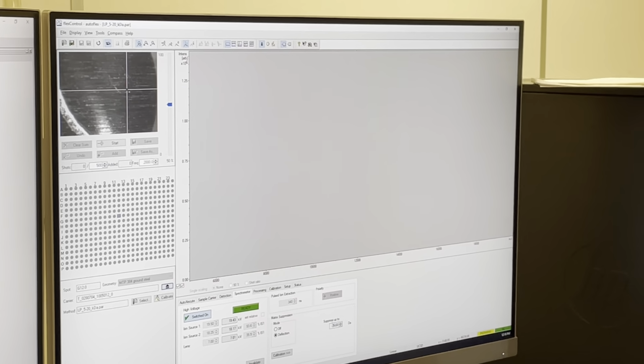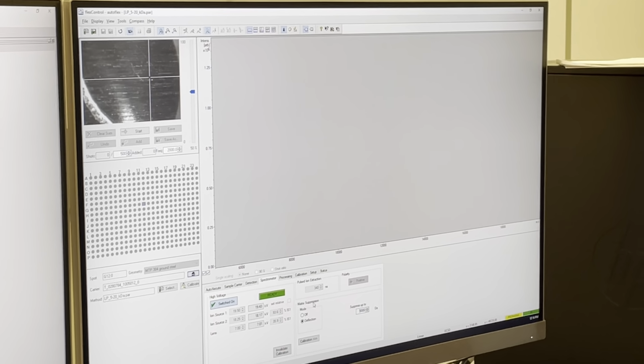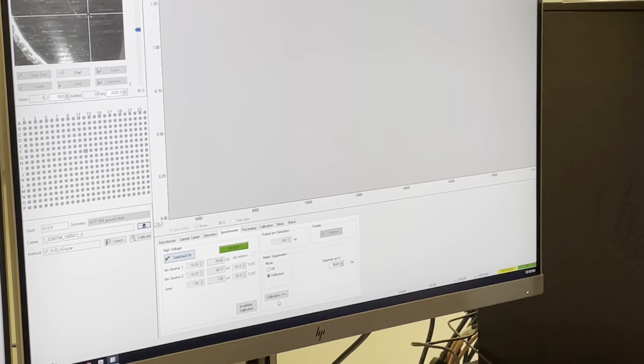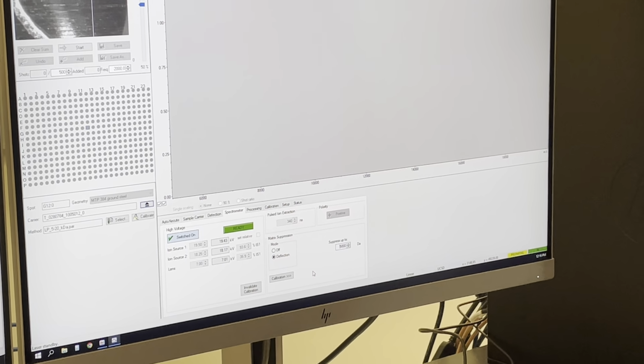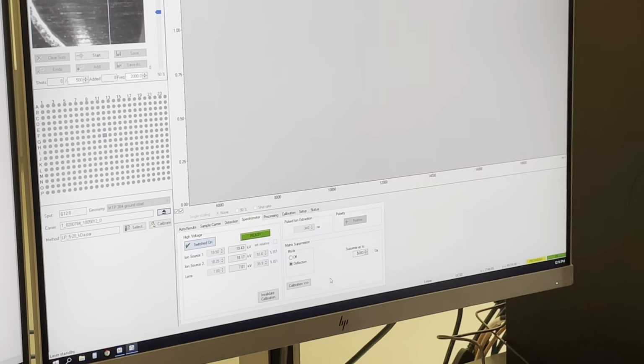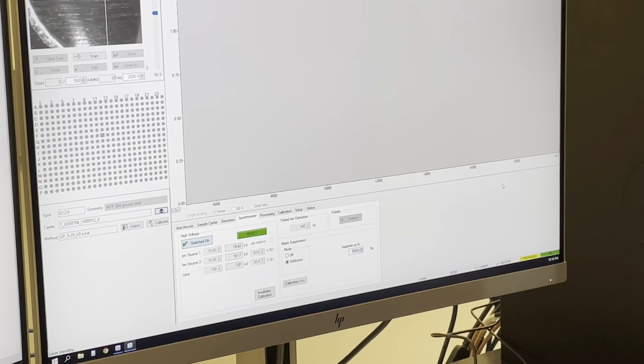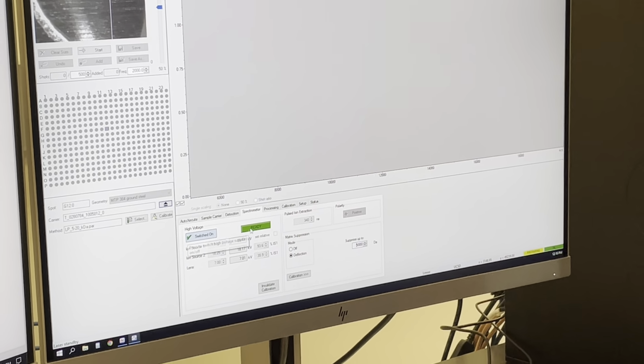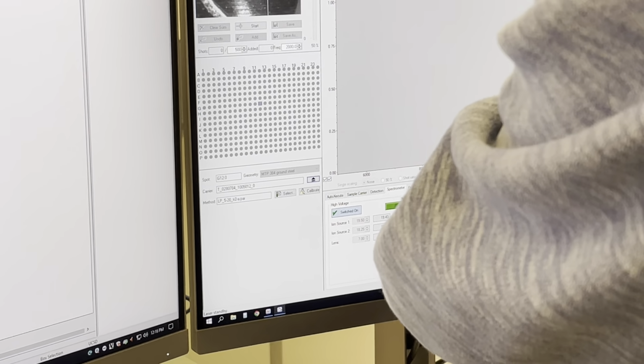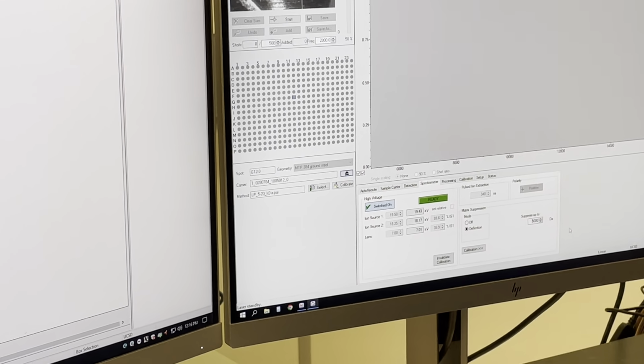This is called matrix suppression. This is important because we don't want to saturate our detector with the matrix ions. It's going to damage it. So after you switch on the high voltage, I have to put the deflection mode on. Always on. Okay, always on.